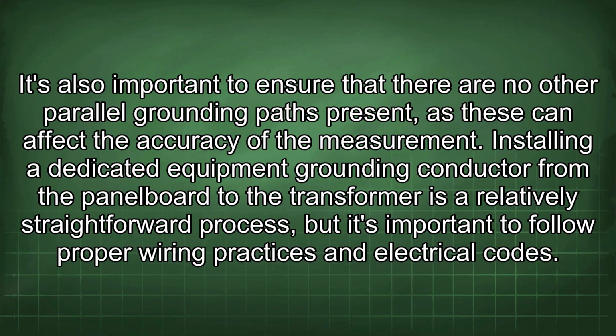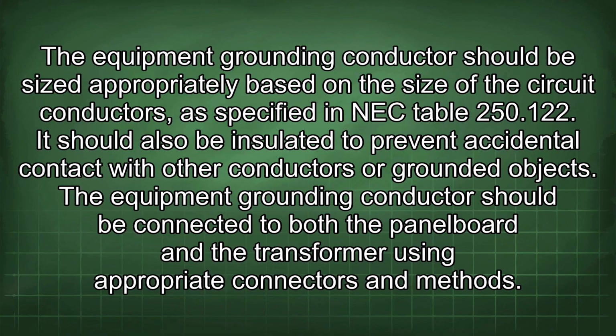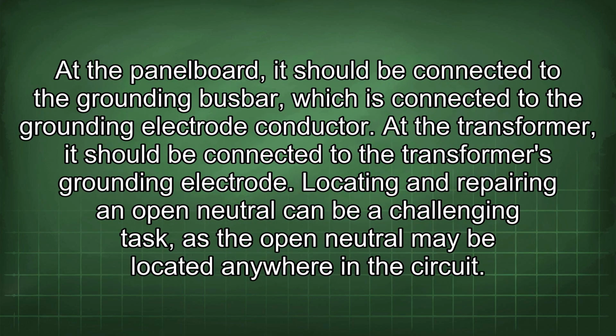Installing a dedicated equipment grounding conductor from the panel board to the transformer is a relatively straightforward process, but it's important to follow proper wiring practices and electrical codes. The equipment grounding conductor should be sized appropriately based on the size of the circuit conductors, as specified in NEC Table 250.122. It should also be insulated to prevent accidental contact with other conductors or grounded objects. The equipment grounding conductor should be connected to both the panel board and the transformer using appropriate connectors and methods. At the panel board, it should be connected to the grounding busbar, which is connected to the grounding electrode conductor. At the transformer, it should be connected to the transformer's grounding electrode.